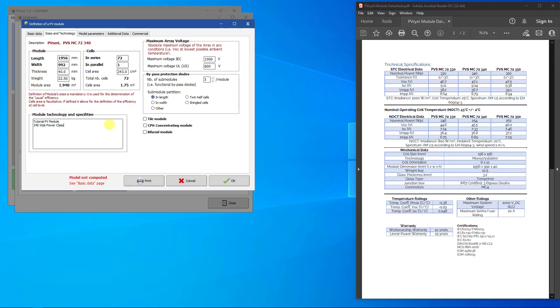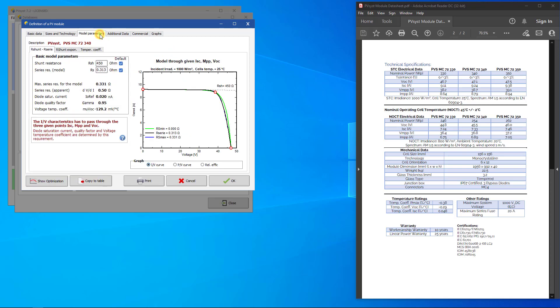Once the sizes and technology are properly set, a tab called Model Parameters will appear. The Model Parameters page defines the parameters that are specific to the PVSYST 1 diode model. They do not show up on the datasheets. Some of these parameters are derived from the values entered in the Basic Data tab. PVSYST calculates values for series and shunt resistance automatically based on the STC measurements in Basic Data. Unless you have measured values for these resistances, you should leave them as their default values.